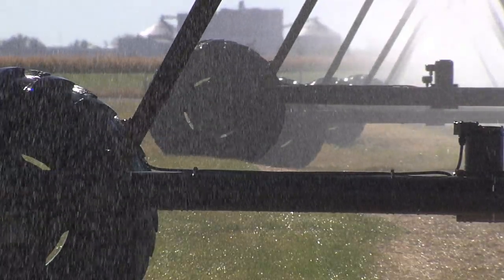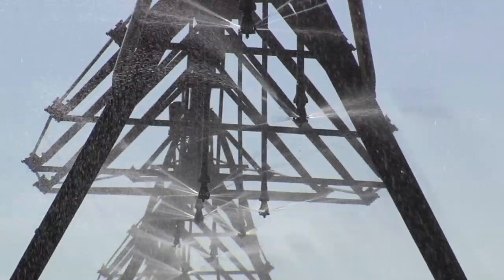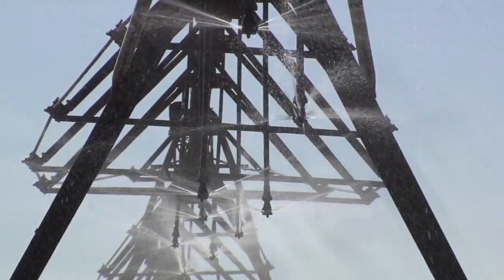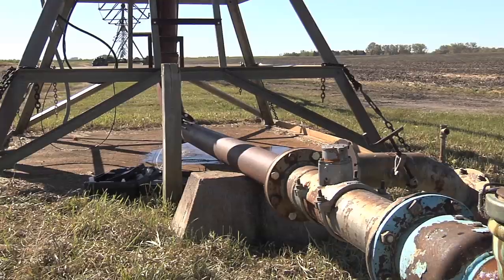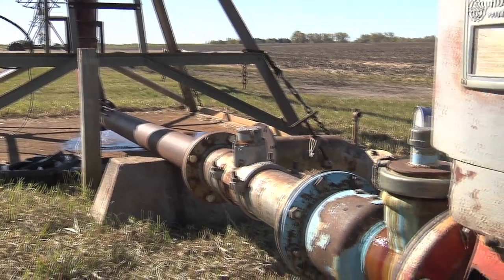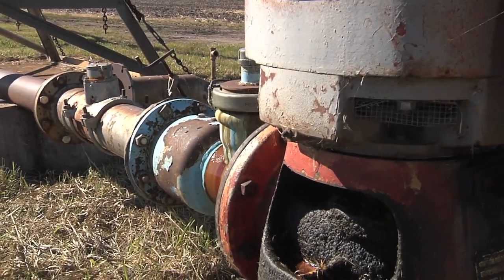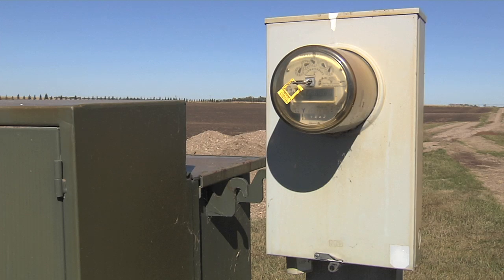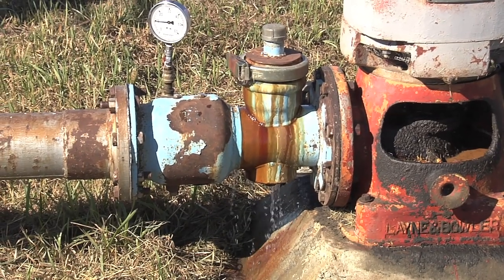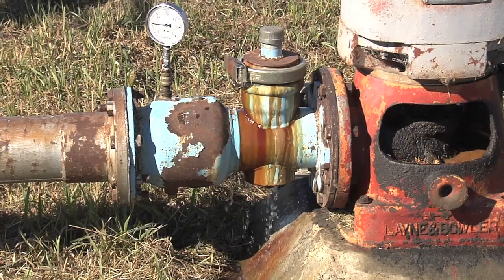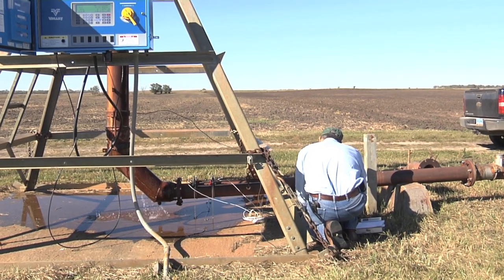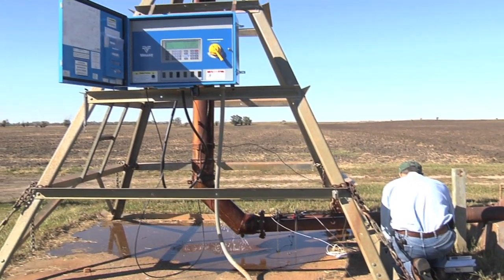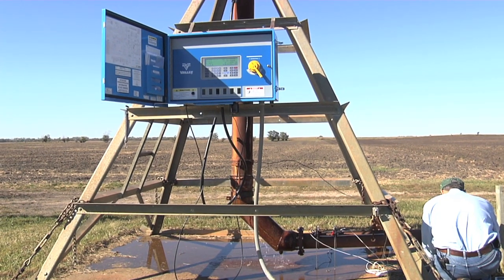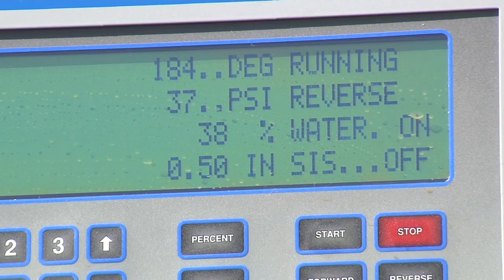They're very popular, they're low labor, but they are pressurized sprinkler systems and they require a pump, obviously, in the water source. The pump is the main user of energy, and it's a large user of energy. People that own irrigation systems, that may be one of the largest energy consumption devices on their entire farm. The only way you can really tell if they are operating efficiently is to do a pumping plant efficiency test, which is really quite simple.